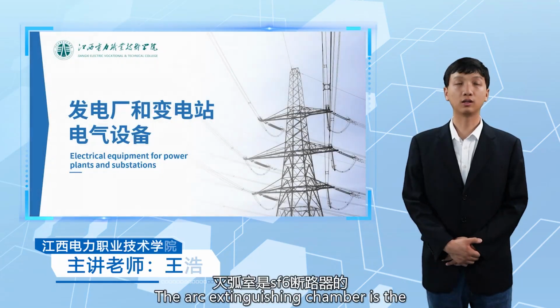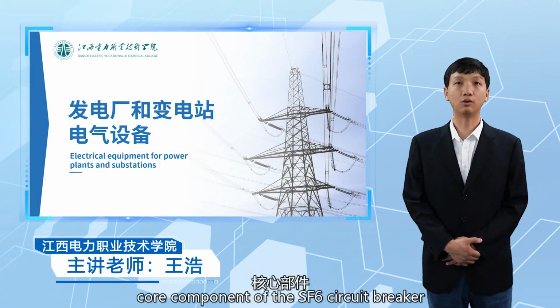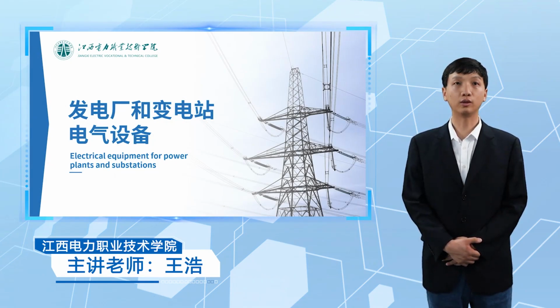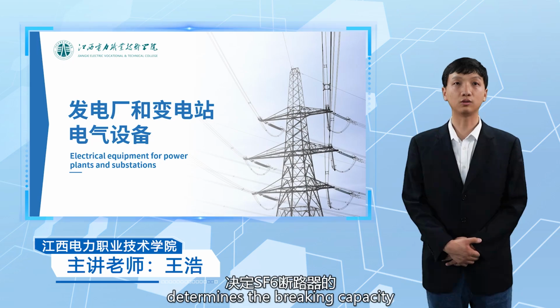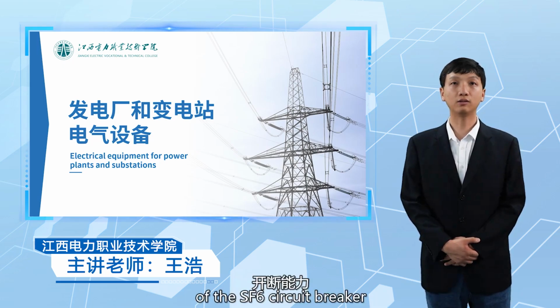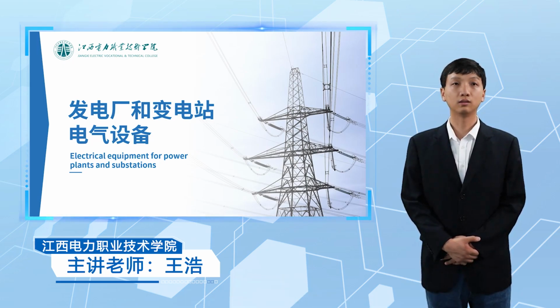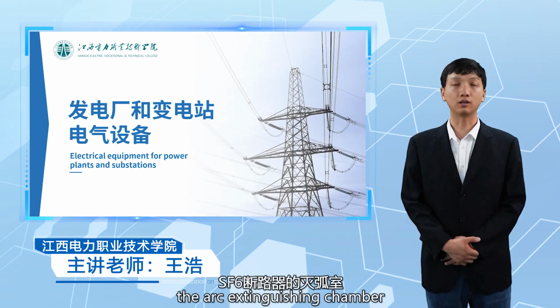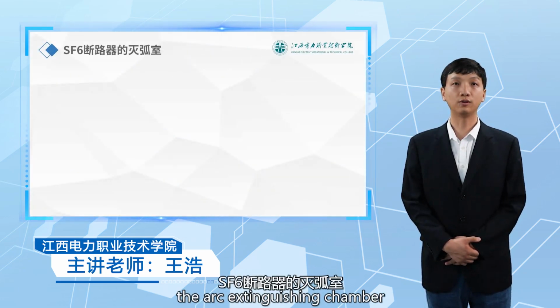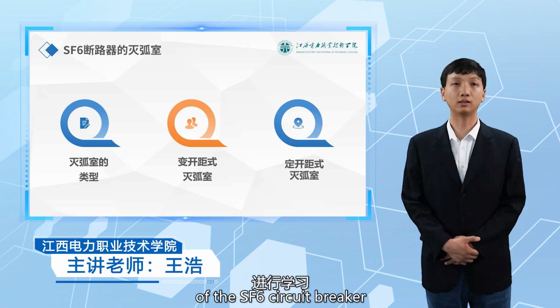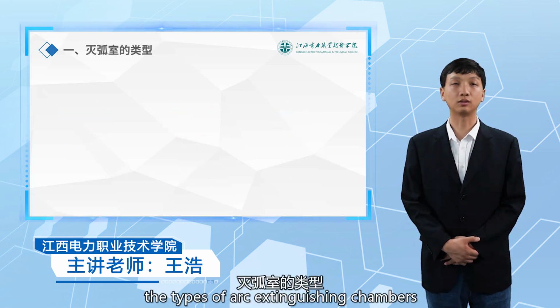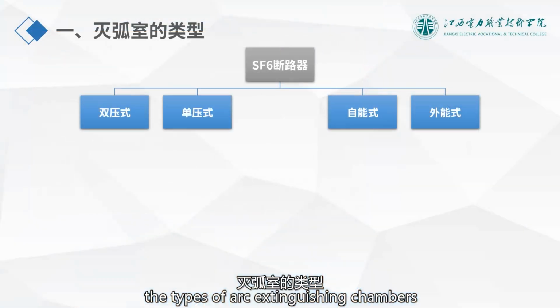The arc extinguishing chamber is the core component of the sulfur hexafluoride circuit breaker. Its performance determines the breaking capacity of the sulfur hexafluoride circuit breaker. Today, we will learn about the arc extinguishing chamber of the sulfur hexafluoride circuit breaker. First, let's understand the types of arc extinguishing chambers.